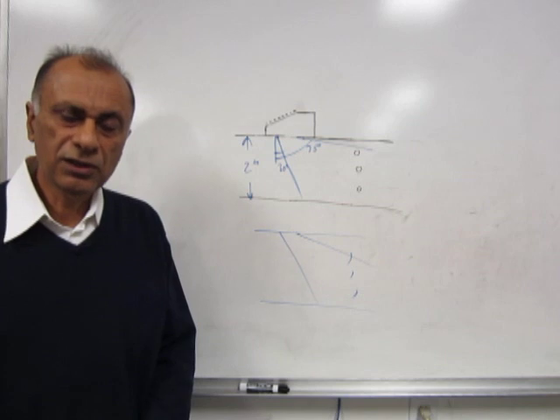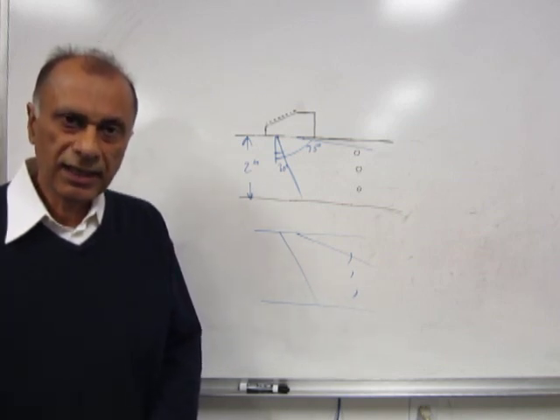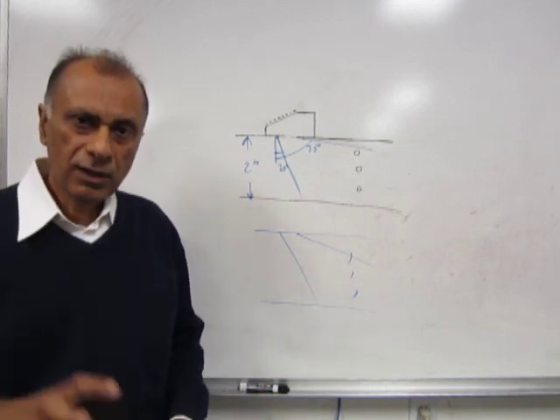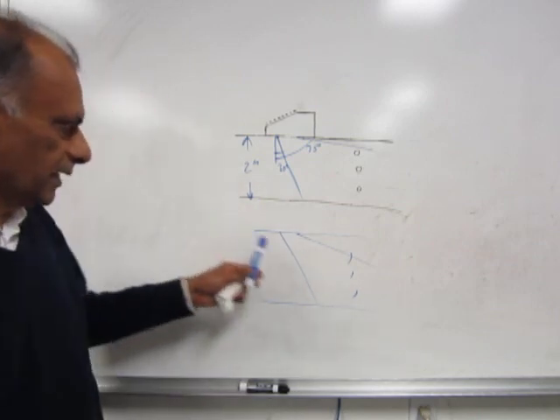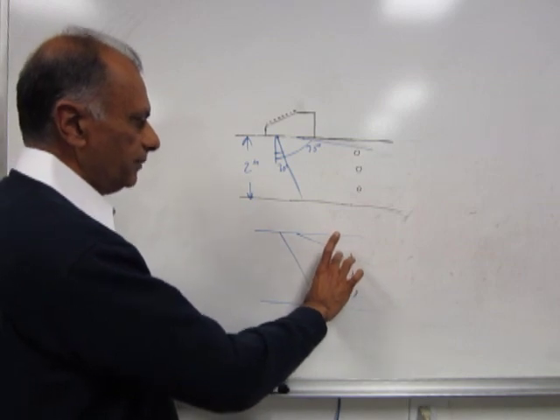Why? Because for conventional angle beam ultrasonics we look at the A-scan, we take the measurements, then from those measurements we plot them on the drawing.